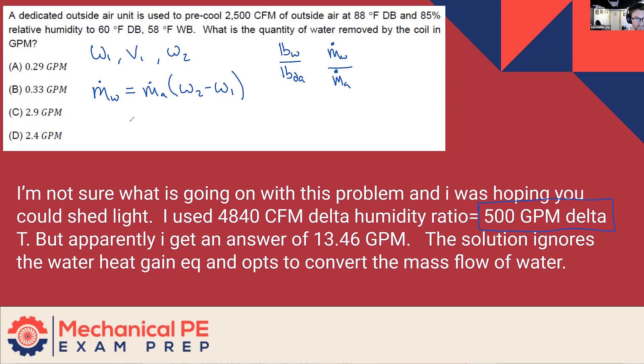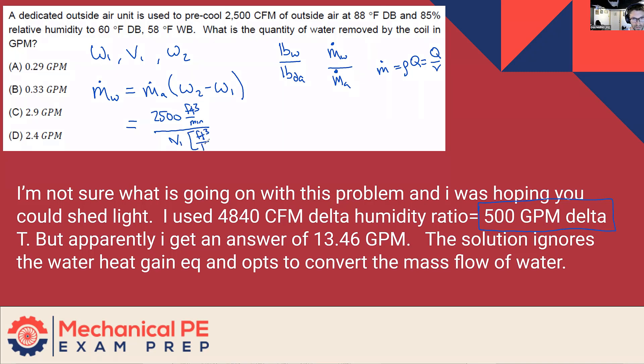In terms of actually applying it, we have the volume flow rate of air — in this case 2500 CFM — and we divide that by the specific volume to get mass flow rate, since mass flow rate equals density times volume flow rate, or equivalently volume flow rate divided by specific volume. Specific volume has units of cubic feet per pound of dry air. Multiplying by the humidity ratio delta, which has units of pounds of water per pound of dry air, and canceling cubic feet and pounds of dry air, you end up with pounds of water per minute.